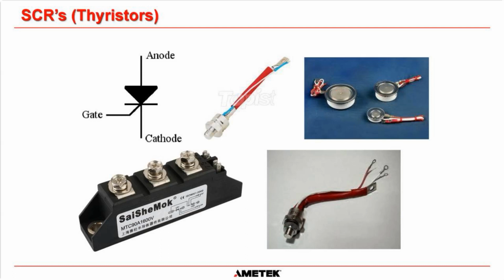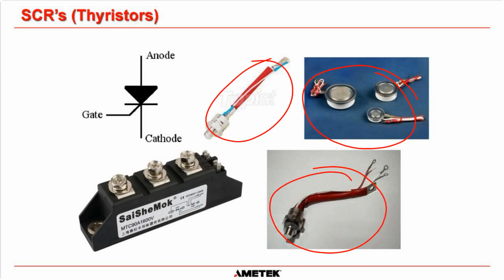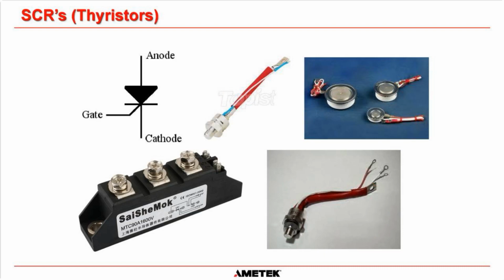So, very good question. Put copper grease, which is electrically conductive, on these, but do not put silicone grease on them. You can put silicone grease on this package. In truth, you could put copper grease on this one too if you wanted, but it would be a waste and messy since there's no electrical connection at the base there. Just use normal silicone compound for this one, but please do use copper grease for this one. It's a very common mistake.